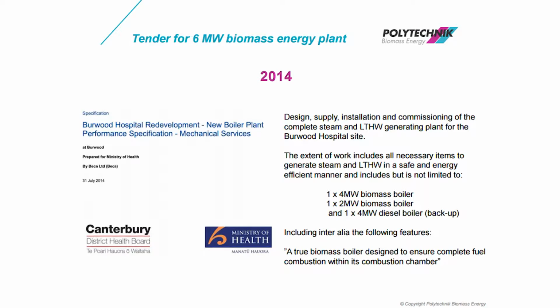So in 2014, the project was awarded to Polytechnik Biomass Energy, and the project involved the supply of steam and low temperature hot water. The extent of the works involved 3 boilers. So there was a 4 megawatt biomass fired boiler, a 2 megawatt biomass fired boiler, and then a 4 megawatt diesel boiler for emergency security of supply. That boiler only ever runs if for whatever reason there's an issue with fuel supply or a breakdown, so it was the security supply. That's all it's there for. It's actually kept hot by the biomass fired boilers, so should they lose steam via the biomass fired boilers, the diesel boiler will kick in immediately and cover the steam requirements for the hospital and hot water.